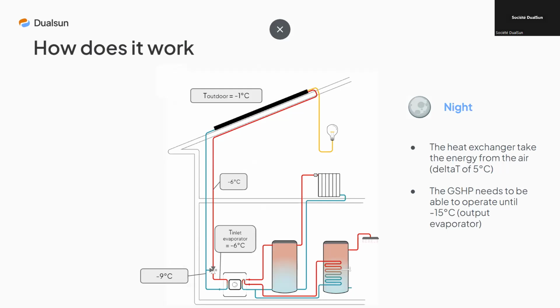It's important to remember that the heat pump can continue to operate as long as the solar flow temperature is not lower than the minimum evaporator temperature. This temperature varies between -10 and -25 degrees, depending on the type of heat pump, and so on. And keep in mind that this is a very important factor to be considered depending on the minimum temperatures in the project in question.